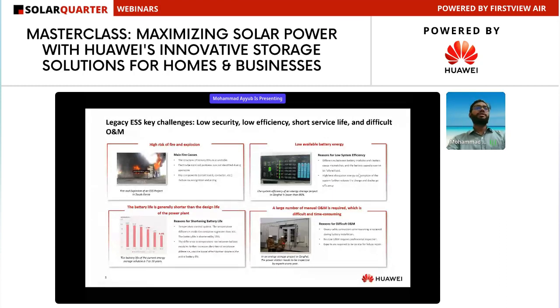If you see in the market, especially for developers, this is very important. If some supplier is committing some capacity, let's say 2 megawatt hour, but they are not actually getting the whole 2 megawatt hour energy capacity usable to them, maybe because of issues related to depth of discharge, or maybe the battery performance itself is not performing as expected.